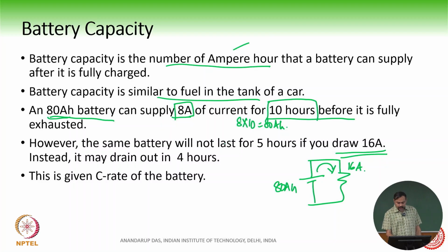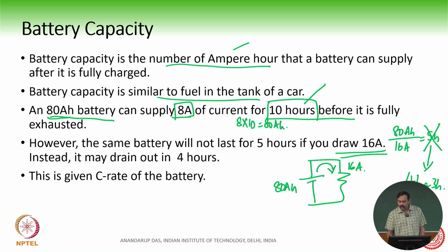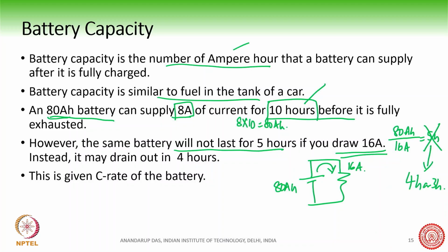You'd expect that since the total capacity is 80 ampere hours, drawing 16 amperes would make it last 5 hours. That's what the math says, but it won't happen. Instead, that 5 hours will drop to maybe 4 or 3 hours. The same battery won't last 5 hours at 16 amperes, because the 80 ampere hour capacity changes when you draw different magnitudes of current from the battery.